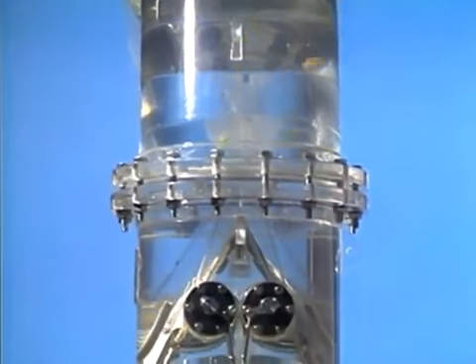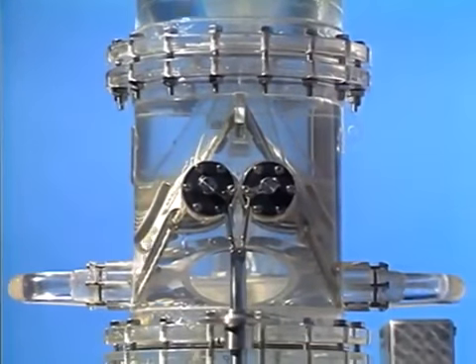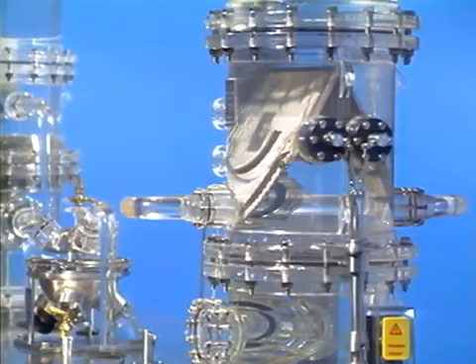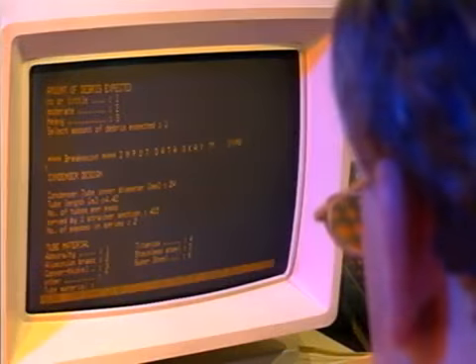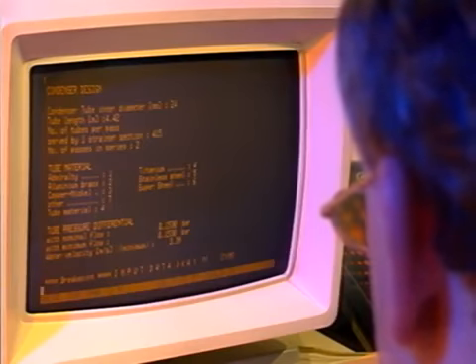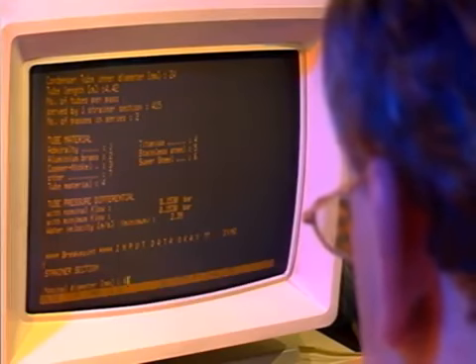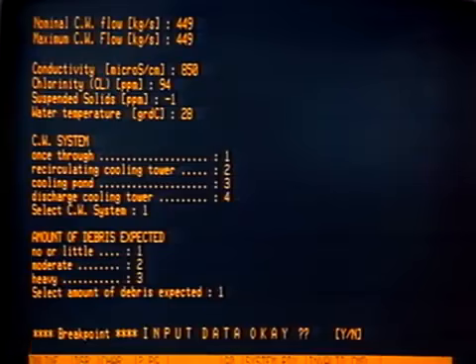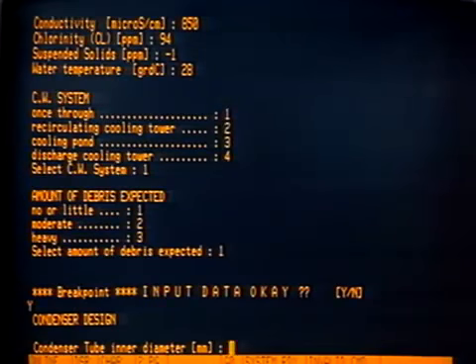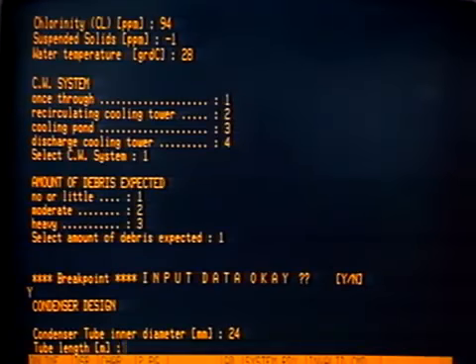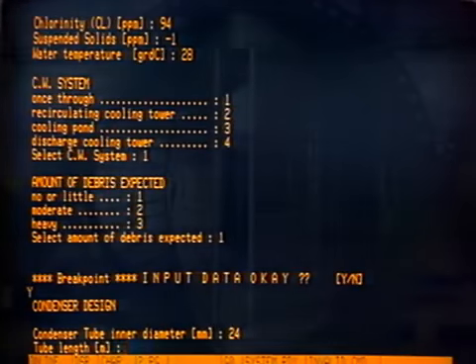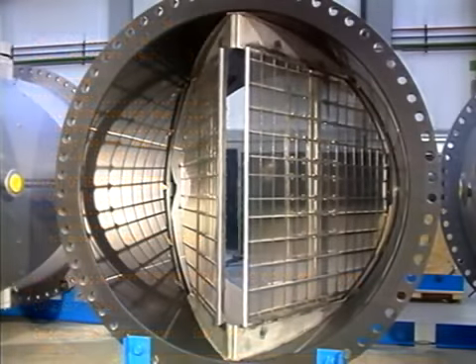After cleaning the condenser tubes, the balls are removed from the cooling water system by the strainer screens. The screens are custom designed by computer, taking into account more than 30 different parameters, like cooling water quality, water volume, or flow rate and pattern. An expert system incorporating the experience of more than 5,000 applications ensures that a screen of the right type, inclination, gap width and material is designed and delivered for each project.